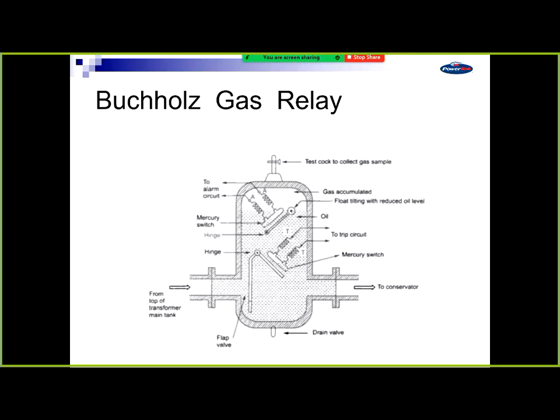Not to them. So that's what a Buchholz relay looks like internally. Unfortunately, I haven't got my laser pointer, but you can see the bottom one. It says trip circuit. So you've got a mercury switch there. You've got a little floating thing there. If a surge of oil comes on the bottom left, it'll knock that plate heavily and tip onto that, make a contact, and out and trip.